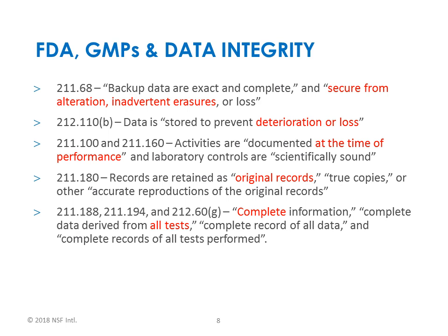When we're starting to look at original records, one of the things that the data integrity guidance documents have provided some clarity on is, what truly is an original record or a true copy of the record. If you look at the terminology that they put forward in these guidance documents, they talk about static and dynamic records. An HPLC chromatogram that's printed out would be a static record, but truly the system that generates HPLC chromatograms, the data acquisition system, is generating dynamic records, because the hard copy printout of a chromatogram, whether it's LC or GC, would not be able to give you the full information that's contained in the electronic record.